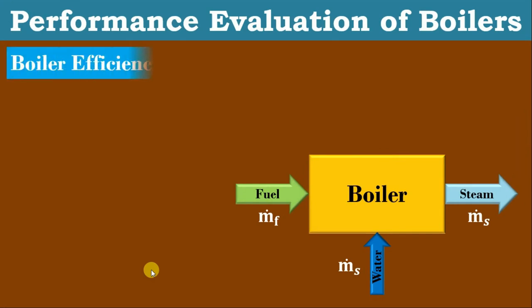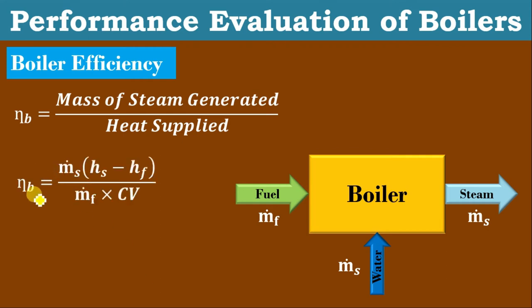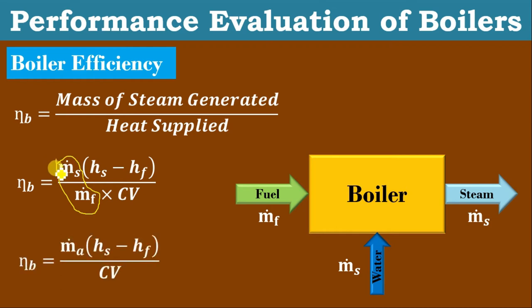In the direct method, that is mass of steam generated divided by fuel supply. The mass of steam generated is nothing but the enthalpy difference multiplied by the mass of water supplied. Divided by heat supplied, which is calorific value multiplied by mass of fuel used. So, efficiency of the boiler is equal to: mass of steam generated (water supplied) × (Hs − Hf), divided by heat supplied Mf × Cv. This equation can be written as: efficiency of boiler = M_dot_A × (Hs − Hf) / Cv.